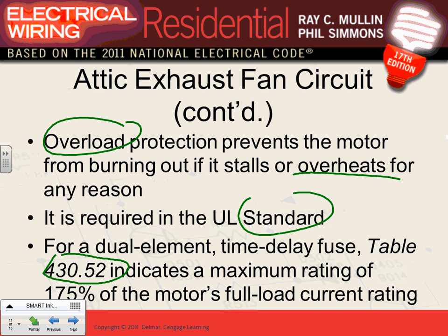430.52. On Thursday, I will be doing a review for you for the test. We're going to use this table. And in this case, they're using a dual element time delay fuse. And this is the multiplier that they use for this one, 175. So if you have 10 amps, it becomes 1.75. That gets you 17.5. What's your next standard size then? 20 amp.